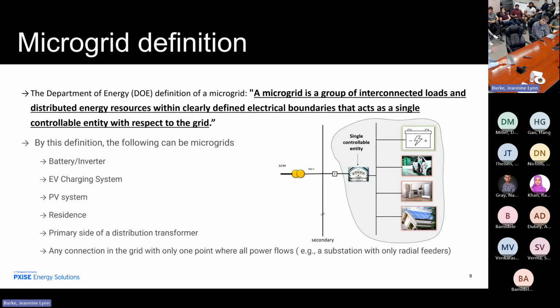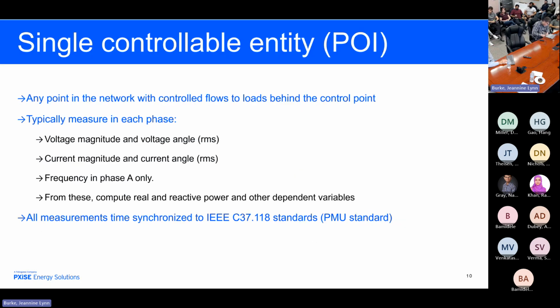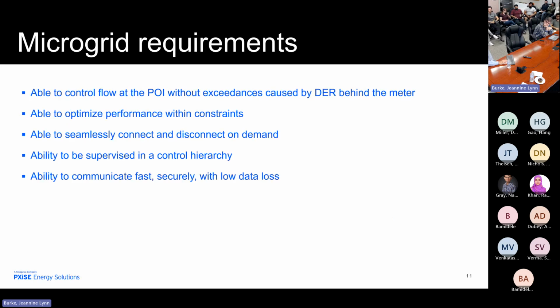Now, when I say control, what type of control are we talking about? And also, what kind of measurements are we talking about? At that point of interconnection, we're talking about the voltage magnitude and the voltage angle, the current magnitude and the current angle, and the frequency. That's all I need to do control of real and reactive power. I'll compute the real and reactive power from these raw measurements. Now, I can also get the measurements directly from a relay through the IEEE standard C37.118, which is typically known as a PMU.